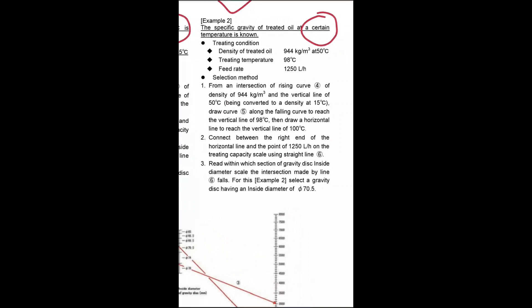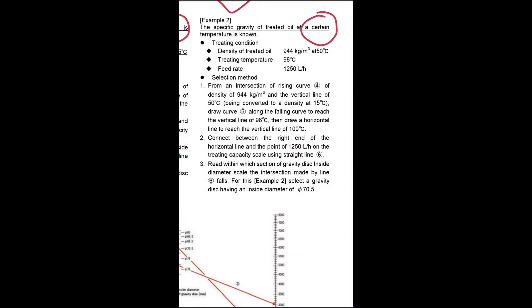We have discussed Case 1 where specific gravity was known at 15 degree centigrade. Now we are going to check Case 2, where we know the specific gravity of the treated oil at a certain temperature other than 15 degree centigrade. We are going to take the case where the density of the treated oil is given at 50 degree centigrade — it could be 60 or 40, it is not compulsory that it is always 50. Here we are taking: density given at 944 kg per meter cube at 50 degree centigrade, treating temperature at 98 degree centigrade, and feed rate at 1250 liters per hour. For these conditions, we are going to check the appropriate gravity disk size.